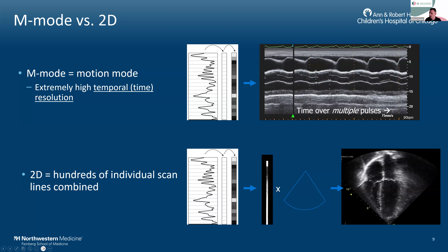You can imagine that the maximum depth of interrogation defines the amount of time that it takes for the furthest object to be detected. So the equation in the upper right here shows the relationship between pulse repetition frequency, or basically how often the scan line can be repeated, and depth of the image. So an object at 10 centimeters will be able to be investigated 10 times less frequently than an object at 1 centimeter depth.